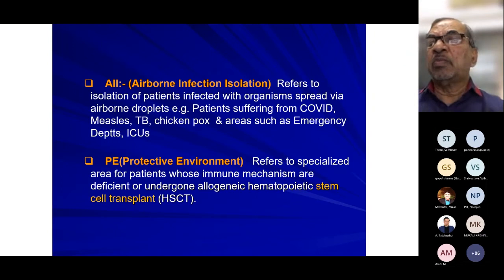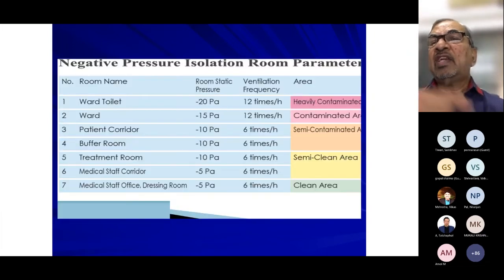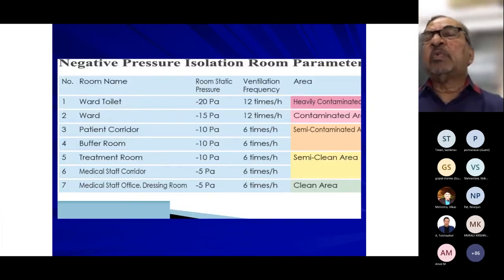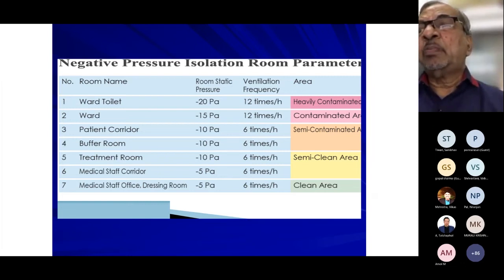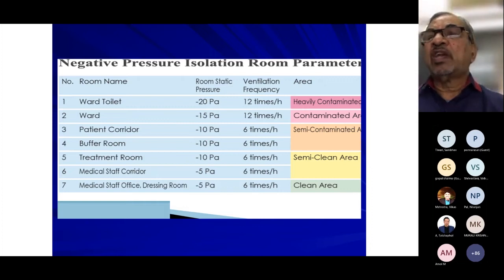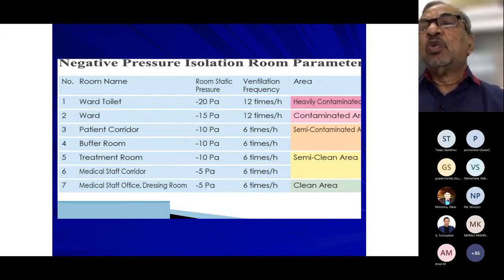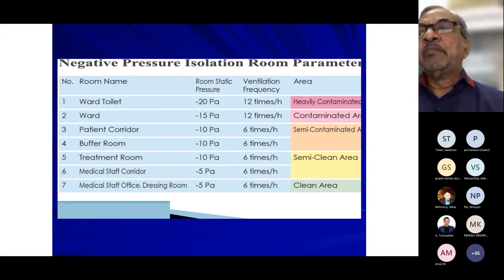Now, people generally ask, sir, how many pascals should we keep, what should be the level? This is already published in the document, where we state the room static pressure in wards, toilets, etc. is minus 20 pascal, with a ventilation frequency of almost 12 times per hour, in heavily contaminated areas.